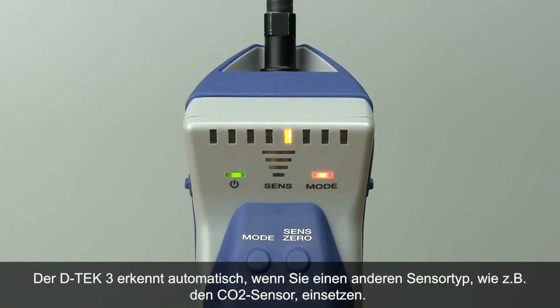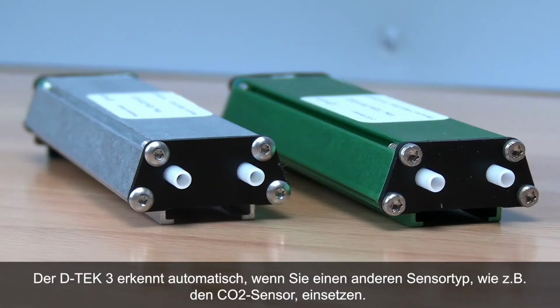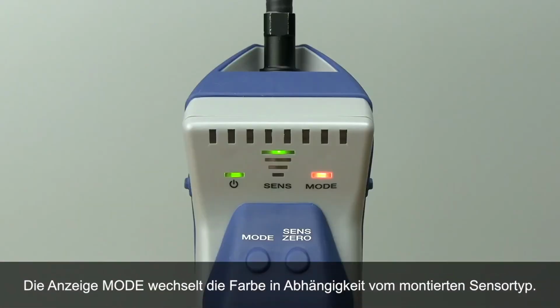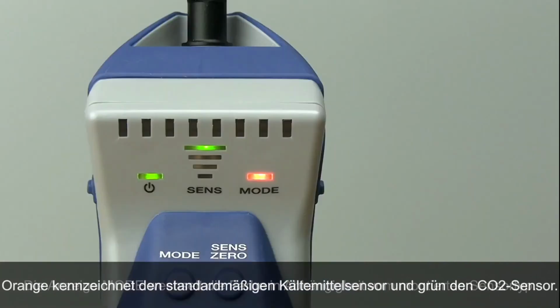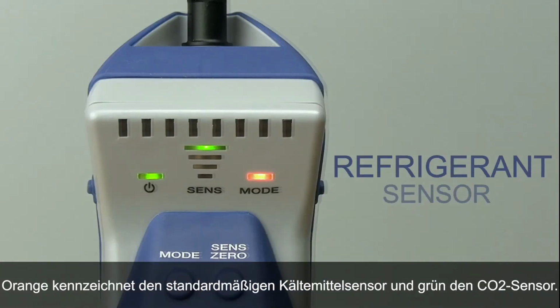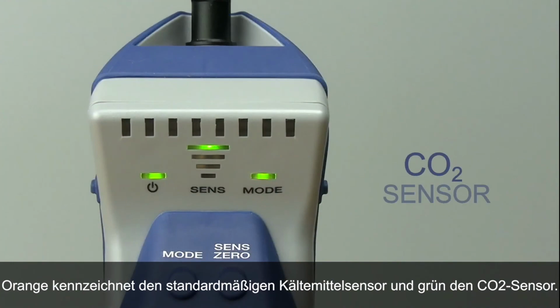D-TEK-3 will automatically sense if you have inserted a different sensor type, like the CO2 sensor. The mode indicator will change color to indicate the sensor type that's installed. Orange indicates the standard refrigerant sensor, and green indicates the CO2 sensor.